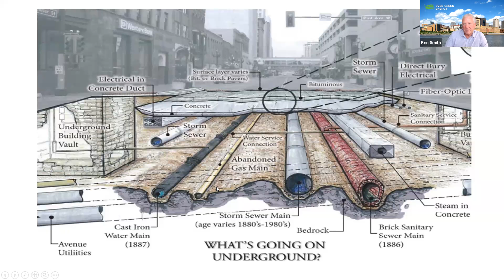We did have some steam remaining, particularly in the healthcare district, towards the 2019 section, around 44th Avenue East, the hospital end towards Essentia and St. Luke's. Once this project was moving forward and investment was being made in Duluth and the hospitals, the hot water network is also being expanded this summer down to the hospitals, which will also be connected to the hot water network. The steam that is used is going to be closed so the condensate is recovered.